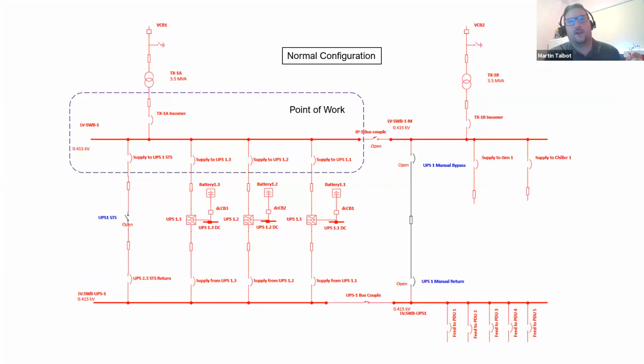Yeah, so again, following on from Marcin's schematics, this is a typical UPS input and output board scenario. And why I've chosen this is, like Marcin says, the LV side potentially has the most dangerous aspects with respect to arc flash. It's normally got the highest incident energy, particularly where we've got transformers which might be close coupled straight onto LV boards. And that reason is that we get the high current. The voltage is there to push between contacts to create the arc, and then the high current is really where the release of heat energy comes from, that does damage to personnel in the immediate area. Unlike HV equipment, LV equipment is rarely rated to deal with that kind of blast.